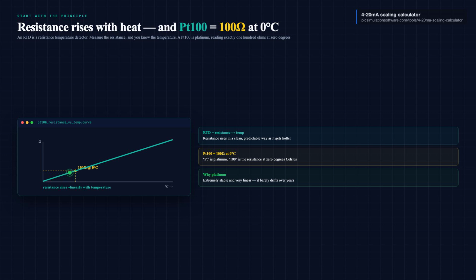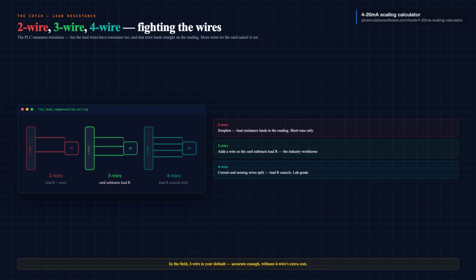Now the catch. The PLC measures resistance, but the wires running out to the sensor have resistance too. And that lead resistance gets added straight onto the reading. On a long cable run, that error can be real degrees. This is why RTDs come in 2, 3, and 4-wire versions. A 2-wire RTD is the simplest. The lead resistance lands directly in the measurement, so it is only for short runs where accuracy does not matter much.